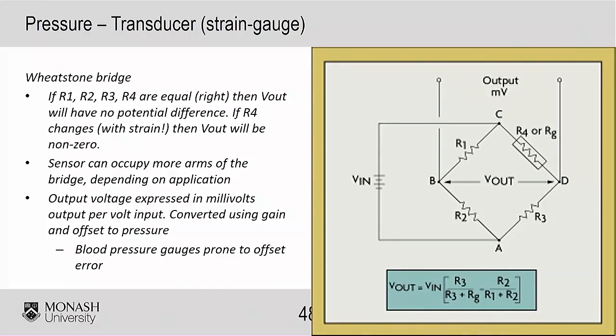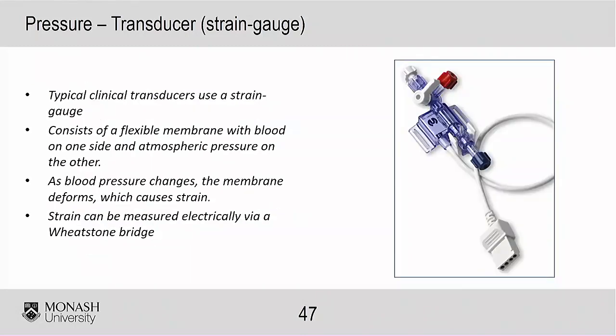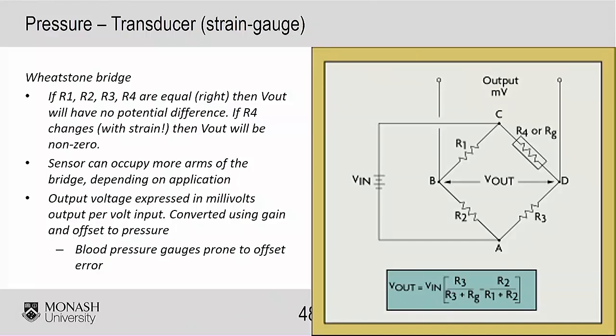So in this case, you could make a resistor on your deformable membrane, so that as the resistance changes, your voltage across B and D changes as well. You can use multiple arms of this as well, depending on the application, but for simplicity's sake, we're only going to talk about changing R4 or RG. And we're not even going to talk about that much. The output voltage is expressed in millivolts output per volt input, and that's converted using a gain and offset to pressure. But these blood pressure gauges are very, very prone to offset error. When you plug them in one time, the very next day you can plug them in and they will be recording something completely different. So can anyone give us an idea of how we might be able to overcome that consistent offset problem?